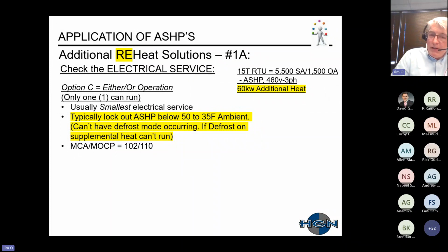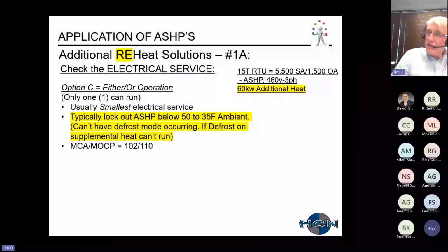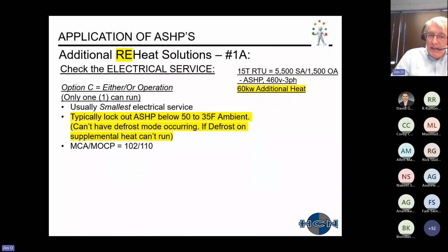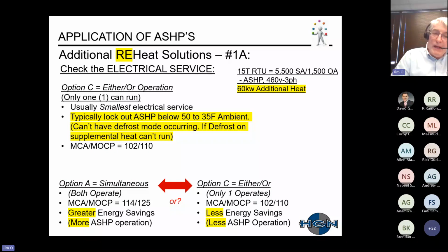Typically what happens is you end up locking out the air source heat pump so that it can't go into defrost mode below a certain ambient temperature. Just realize once again that your electric heat cannot run in conjunction with your refrigeration system. So if you compare option A versus option C, you can see the difference in the electrical service.